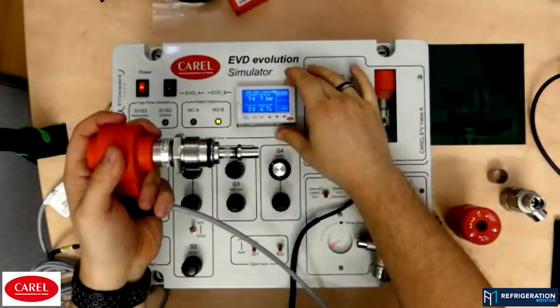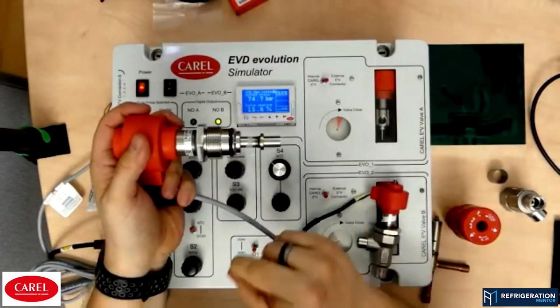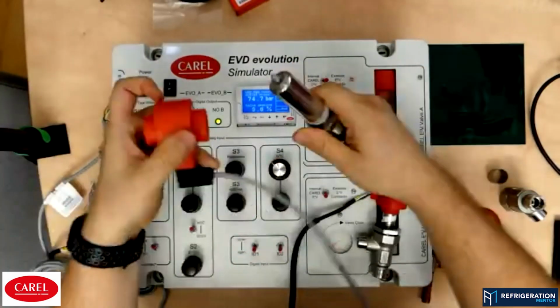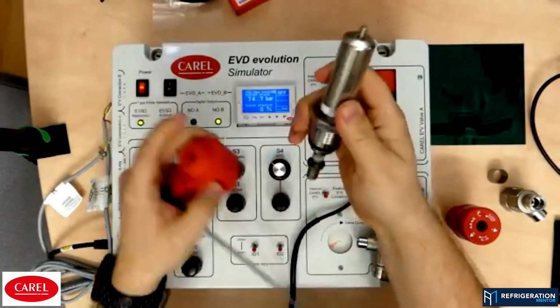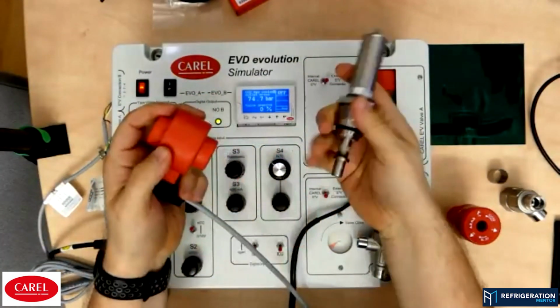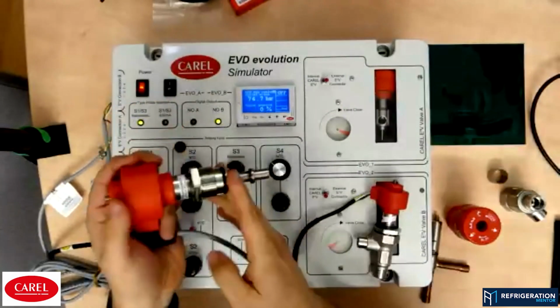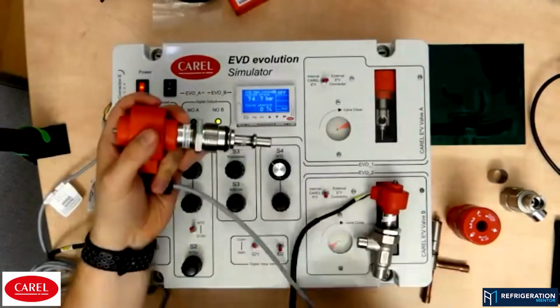Our controller has no idea what the valve is really doing. When I disconnect our data from our actuator, so from the valve body, so to speak, it will have no idea where it is. And exactly this was the problem.